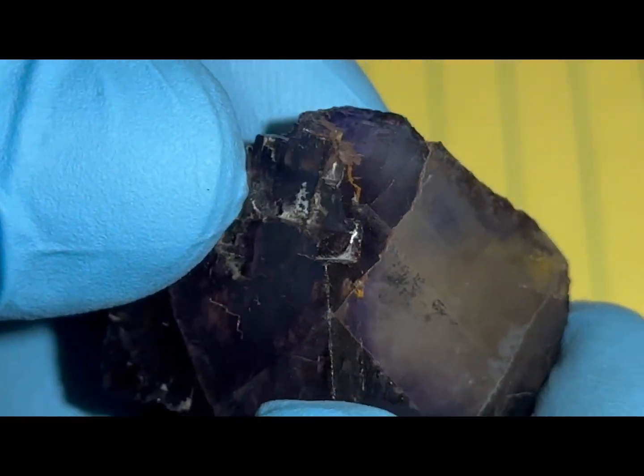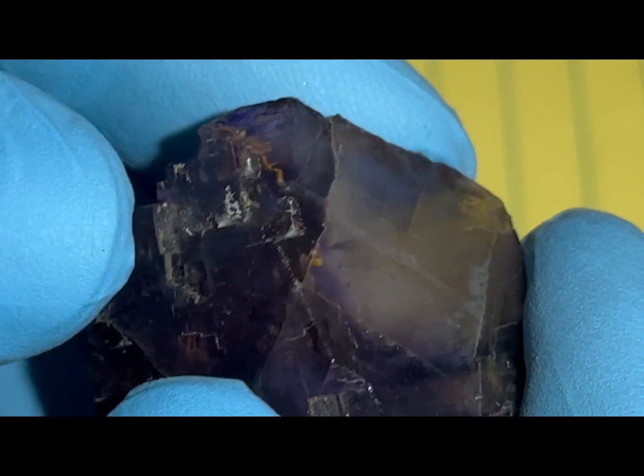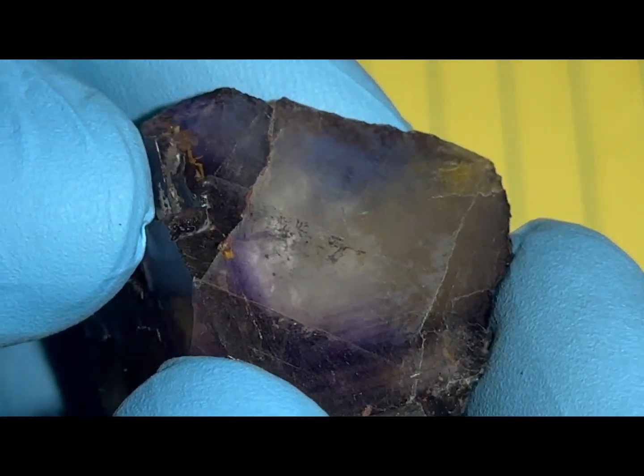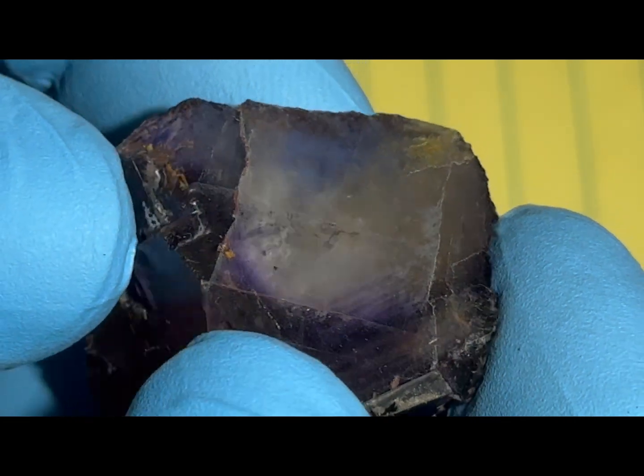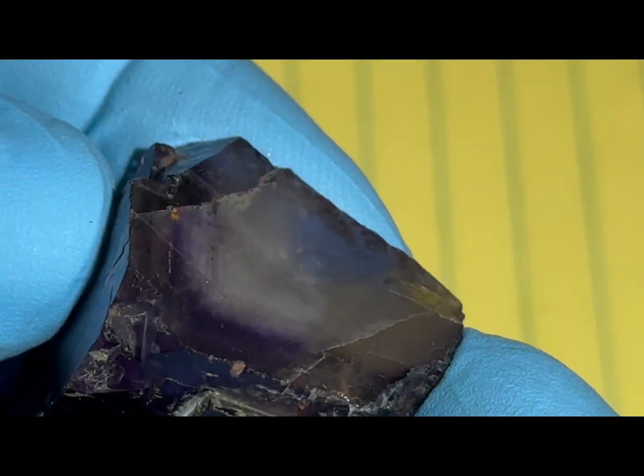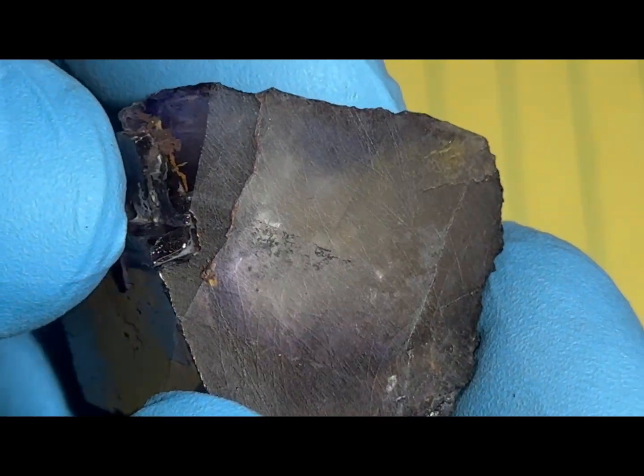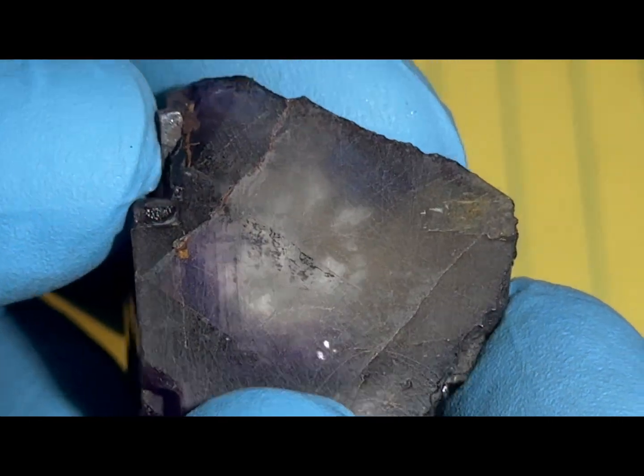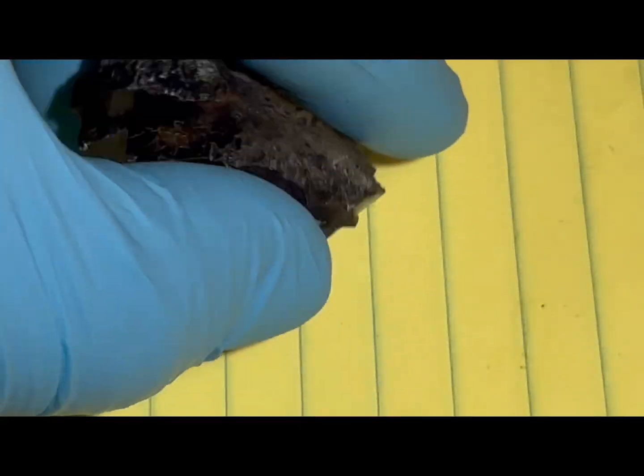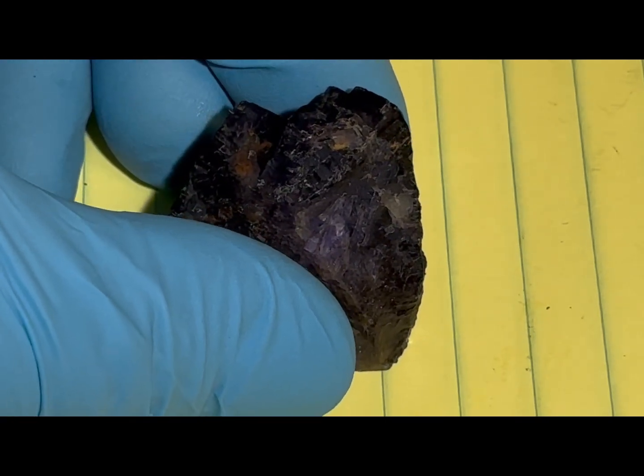For what it's worth, I've restored a whole bunch of scintillation detectors over the years, and when removing the old sodium iodide crystals from detectors that were built in the 1950s, their optical clarity is way, way, way worse than this. Let's set this aside and I'll show you a typical sodium iodide crystal from 1955.